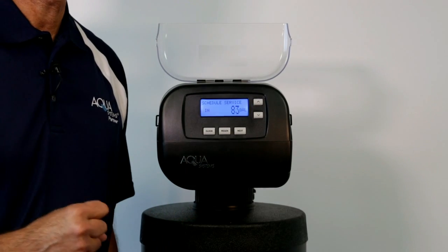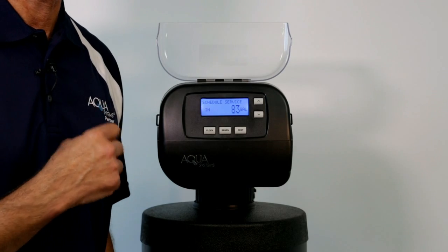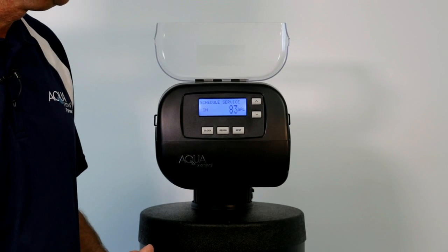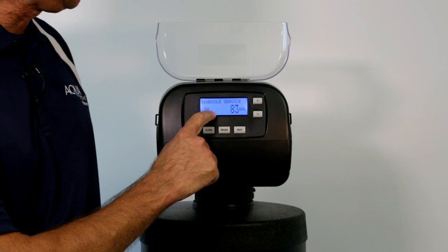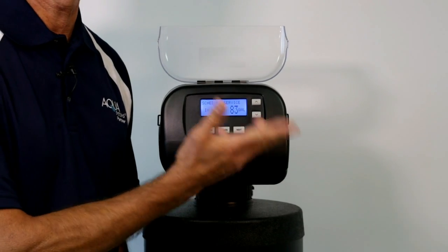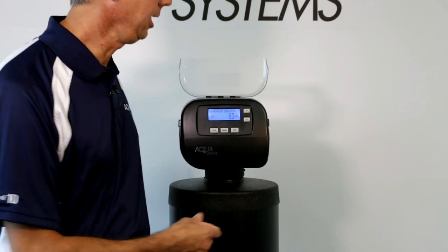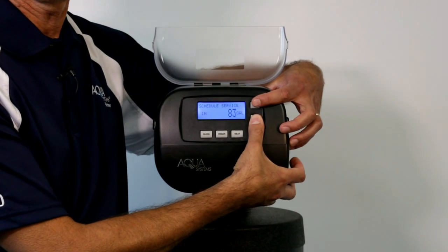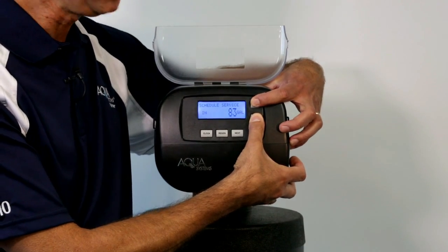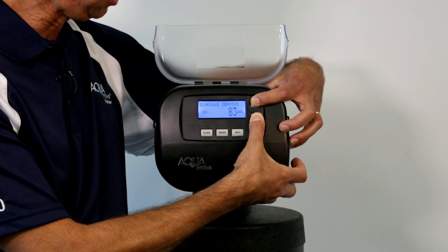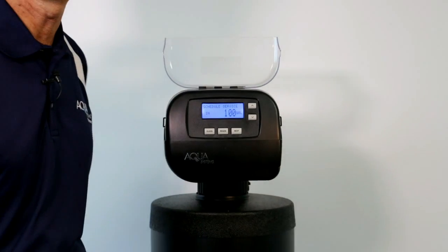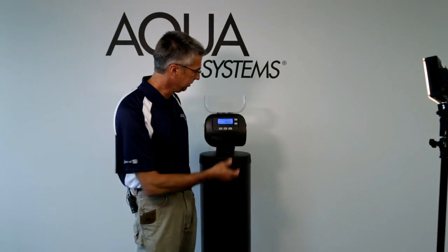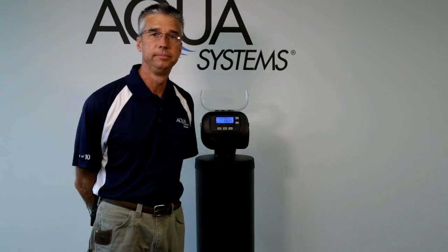Now I happen to set this on 100 gallons because we were going to cheat the system so we could get a rapid service alarm, which we just showed you in the last segment. So now I went through and I see that it says that service is due in 83 gallons, but I know that the service alarm setting is higher than that. So at any point in time while I'm viewing the time or the gallons remaining, I can push the up and the down arrows, and I will reset that to its original setting. So as it went back to 100 gallons, we're there. And then I hit next, and I've escaped the programming mode.